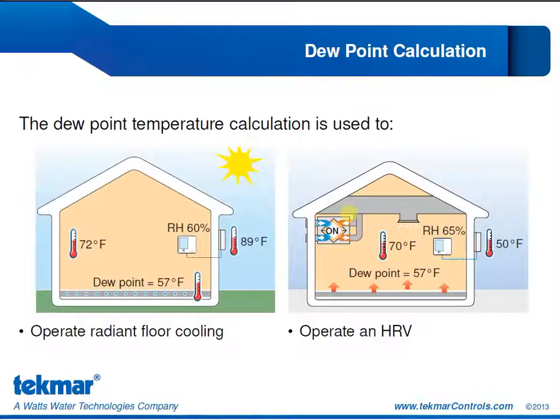We also use relative humidity for the dew point calculation. And this dew point temperature is necessary for two operations, for radiant cooling and to operate an HRV. For radiant cooling, we're going to be pairing the 557 with the 406 house control. And in this case, the 406 house control will be using the relative humidity measurement provided by the 557 to do the dew point temperature calculation in order to reset the water temperatures for radiant floor cooling, making sure we avoid condensation. We talked about this operation in greater detail in the first webinar, so feel free to refresh by looking at that first webinar again on our website.